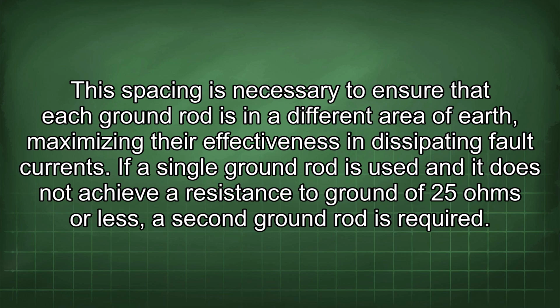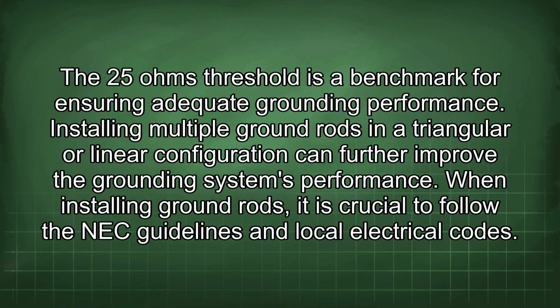If a single ground rod is used and it does not achieve a resistance to ground of 25 ohms or less, a second ground rod is required. The 25 ohms threshold is a benchmark for ensuring adequate grounding performance. Installing multiple ground rods in a triangular or linear configuration can further improve the grounding system's performance.